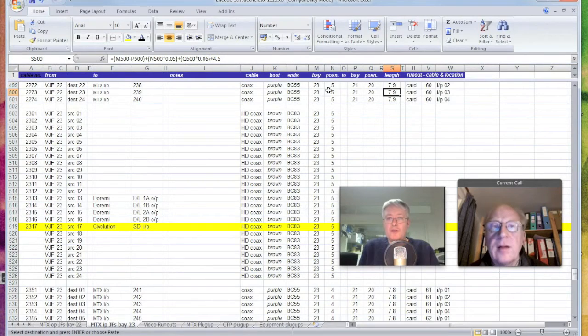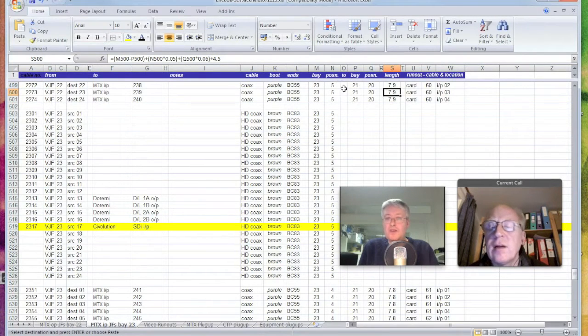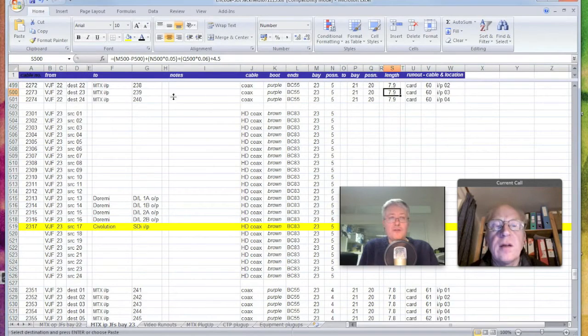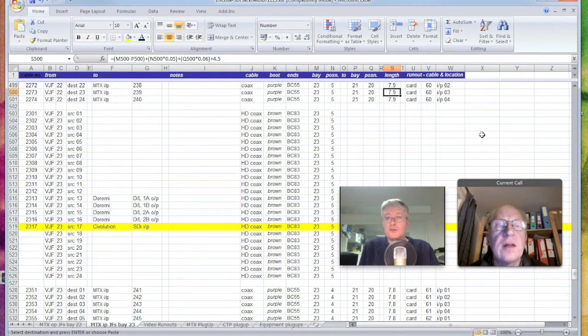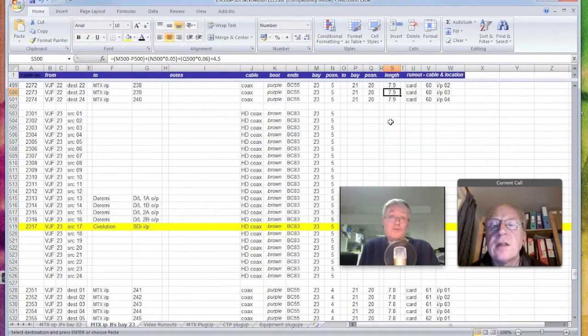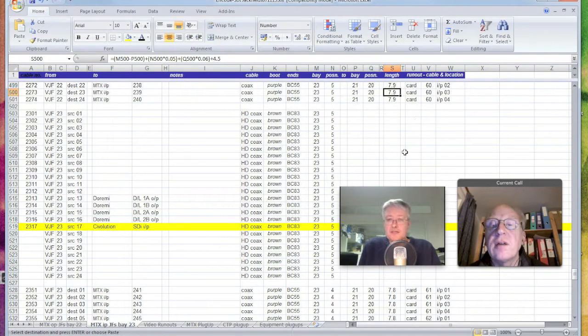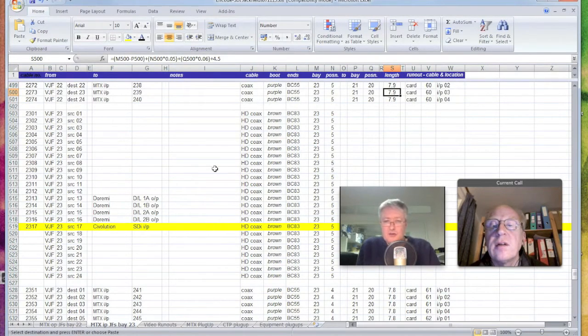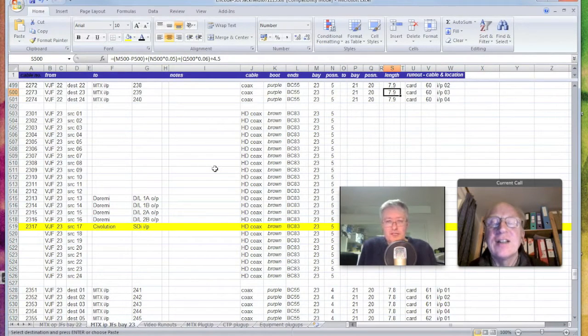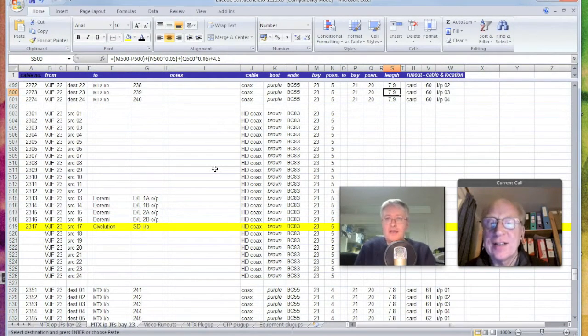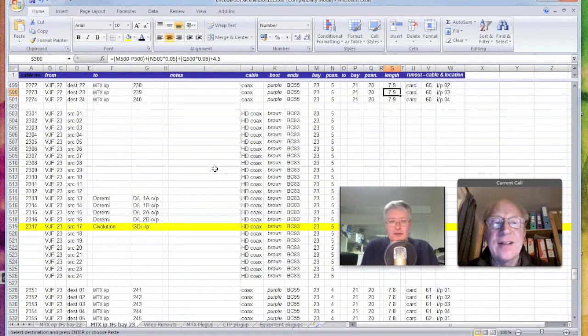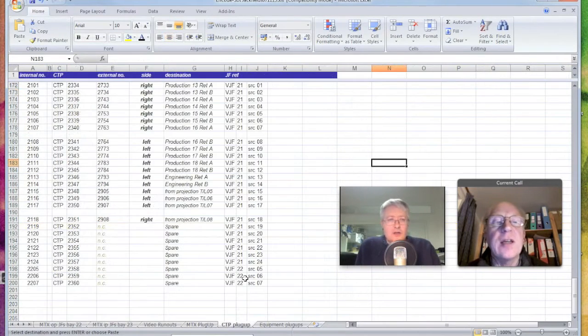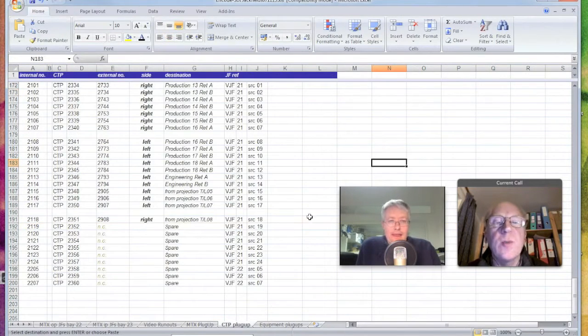And so down a long run of racks you can calculate lengths very very accurately. And I found, using this method and then just looking at the values that Tony the Wireman would have written on in pencil, I've refined my formula now so that so long as I get the bay number and the U-age position correct, I know I'm within centimeters of what he'd calculate. And there's not very much scrap cable at the end of the day. Excellent. And that's meant we've with some confidence been able to cut thousands of cables off-site ready to get on-site, plug up and dress them in.